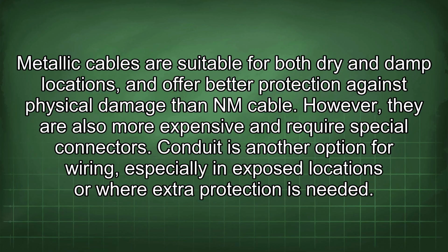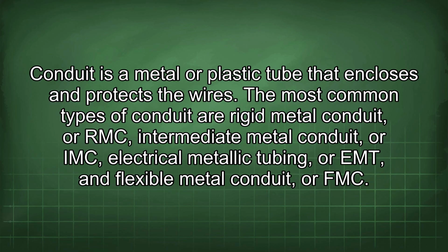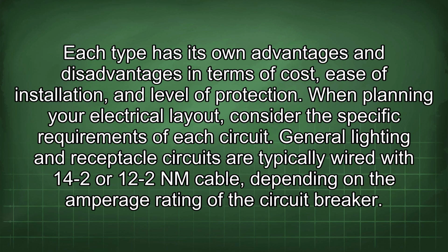Conduit is another option for wiring, especially in exposed locations or where extra protection is needed. Conduit is a metal or plastic tube that encloses and protects the wires. The most common types of conduit are rigid metal conduit, or RMC, intermediate metal conduit, or IMC, electrical metallic tubing, or EMT, and flexible metal conduit, or FMC. Each type has its own advantages and disadvantages in terms of cost, ease of installation, and level of protection.